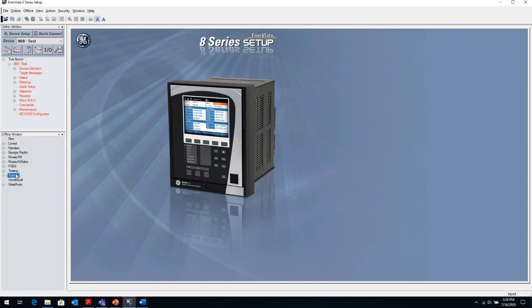So when we come into the EnerVista setup software, there's two windows that we first see when we enter the EnerVista software window. The top window, which we call the online window, and the bottom window, which we call the offline window. The online window is when we're connected directly with the relay. So everything we do in the online window is live on the relay. So right now I have a relay on my bench here connected. So I'm going to go into that relay.